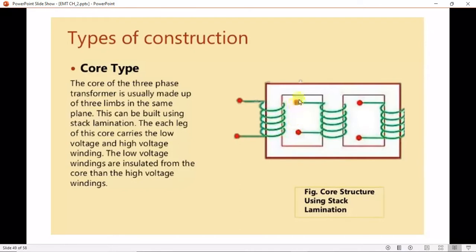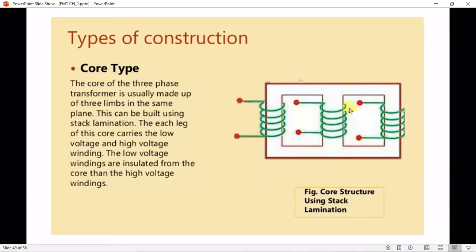The low voltage windings are easier to insulate and are placed closer to the core than the high voltage coils. The later windings are wrapped around the former with insulative material between them. This construction has three windings magnetically linked with each other, with one winding using the other pair of limbs as a return path for its magnetic circuit.